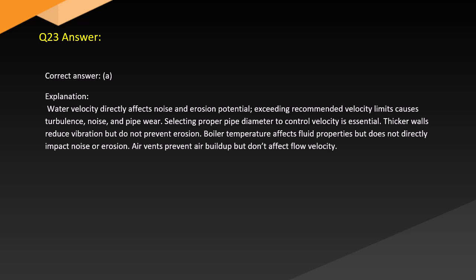Answer. Correct answer: A. Explanation. Water velocity directly affects noise and erosion potential. Exceeding recommended velocity limits causes turbulence, noise, and pipe wear. Selecting proper pipe diameter to control velocity is essential. Thicker walls reduce vibration but do not prevent erosion. Boiler temperature affects fluid properties but does not directly impact noise or erosion. Air vents prevent air buildup but don't affect flow velocity.